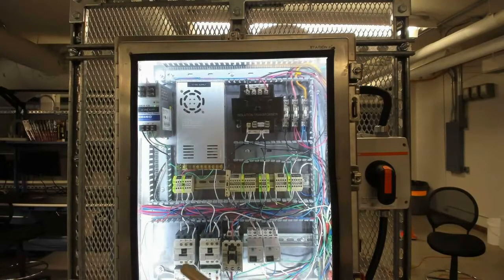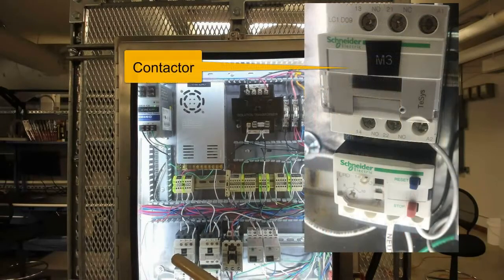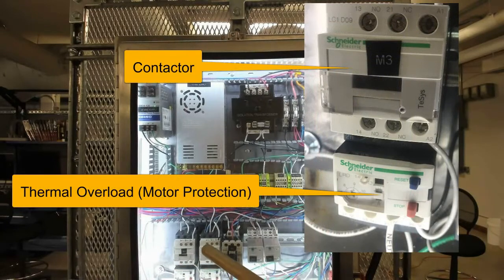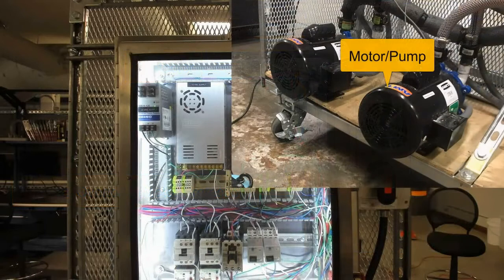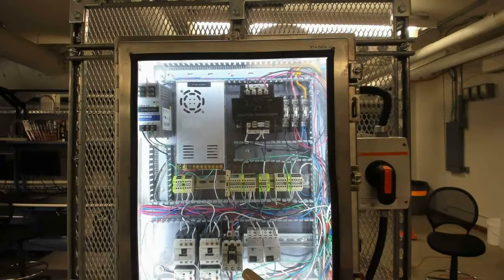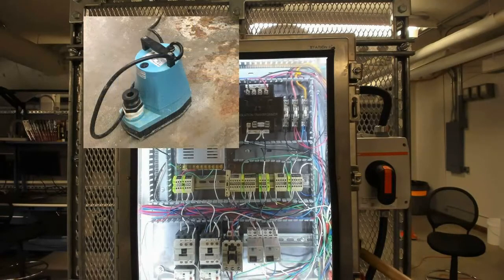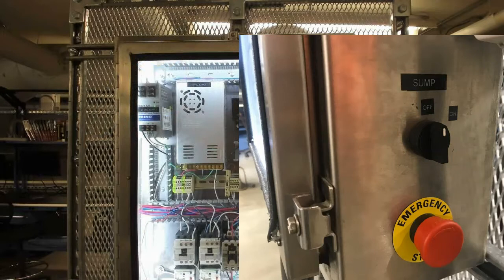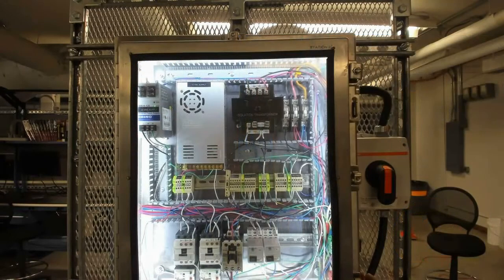Down here we have a motor starter, so we have the contactor and then the thermal overloads. Another contactor with thermal overloads. So these run our 2 motors that drive the pumps. This contactor that's right here that is actuating is our contactor for our heating element. So the heating element is being turned on and off right now to heat our heat transfer fluid. There is a sump pump to help fill the training skid, and then of course an emergency off button here in case we needed to turn all power off.